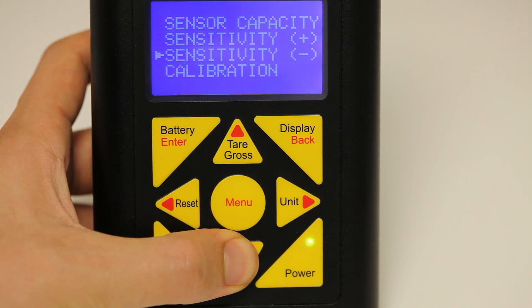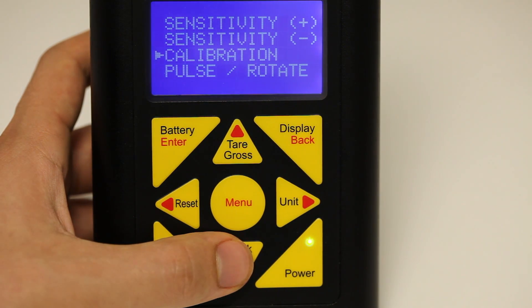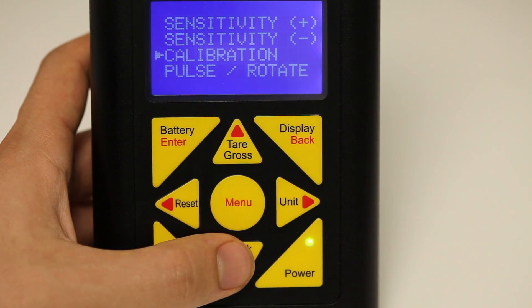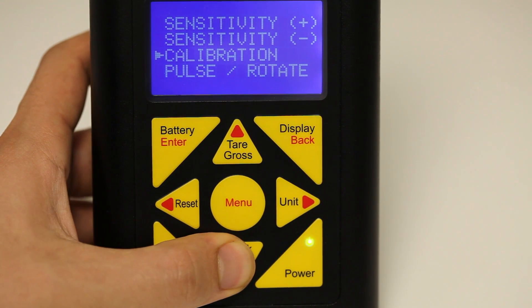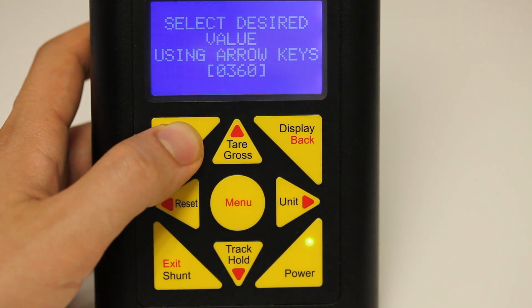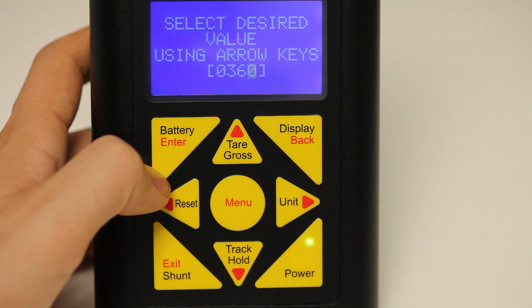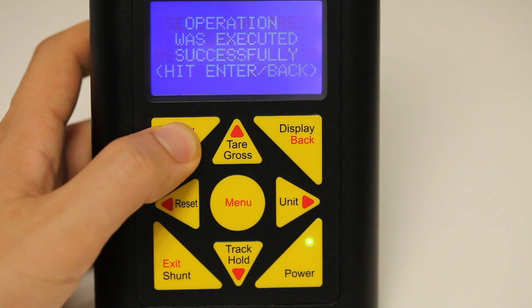Press down and you will see calibration is highlighted. Calibration is a method to perform a live calibration, and we will go over that method after we have set up the profile using known information. Press down to highlight pulse rotation. Press enter to go into pulse rotation. Set the number of pulses that would be available from your load cell, if applicable. For our example, our TRS-605 has 360 pulses out per revolution. Press enter to enter in the value.